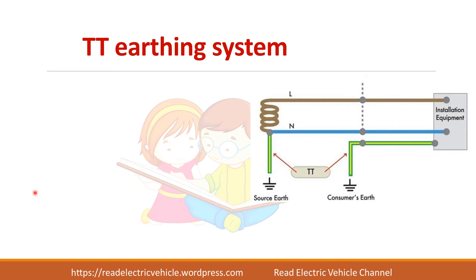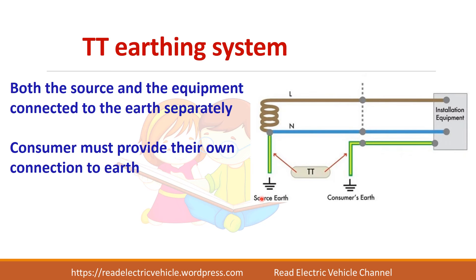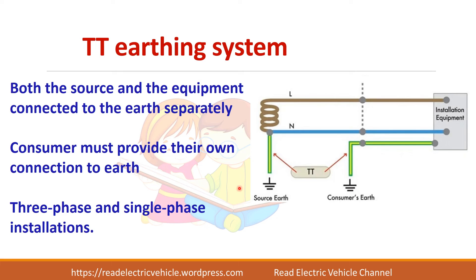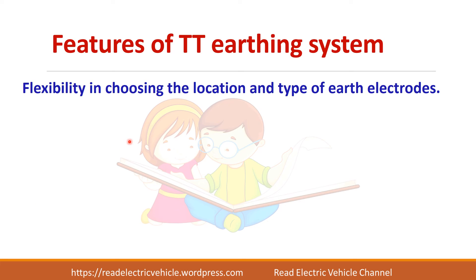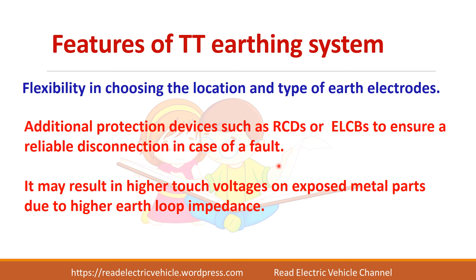In the TT earthing system, both letters T mean direct connection to the earth — the source is connected to earth and the consumer is also connected to earth. Sometimes the consumer has to provide their own earth connection, as it may not be provided by the distributor. This is normally preferred for single-phase and three-phase installations. The TT system offers flexibility in choosing the location and type of earth electrode, but a major drawback is the need to install protection devices like an RCD or ELCB, and it may result in higher touch voltage.